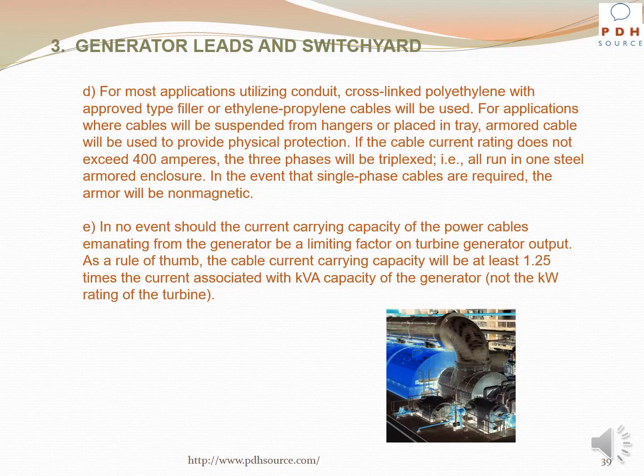For applications where cables will be suspended from hangers or placed in tray, armored cable will be used to provide physical protection. If the cable current rating does not exceed 400 amperes, the 3 phases will be triplexed, i.e., all run in one steel armored enclosure. In the event that single-phase cables are required, the armor will be non-magnetic. In no event should the current carrying capacity of the power cables emanating from the generator be a limiting factor on turbine generator output. As a rule of thumb, the cable current carrying capacity will be at least 1.25 times the current associated with kVA capacity of the generator, not the kilowatt rating of the turbine.